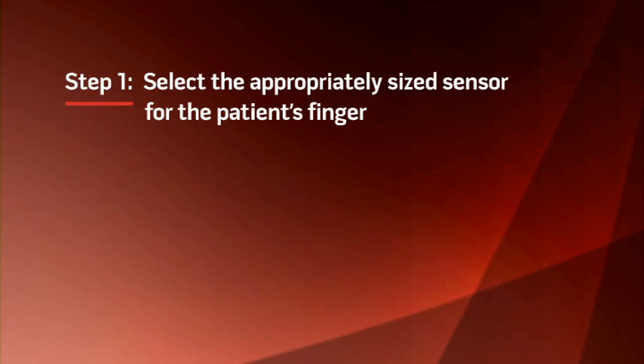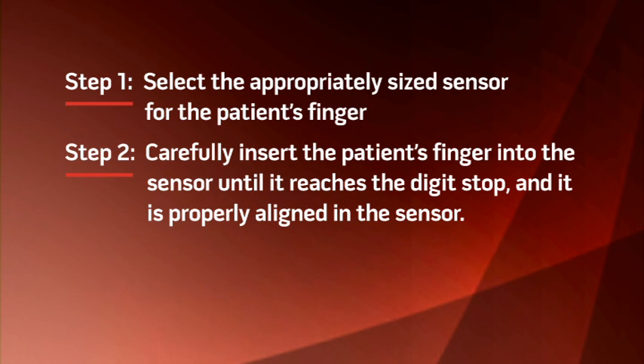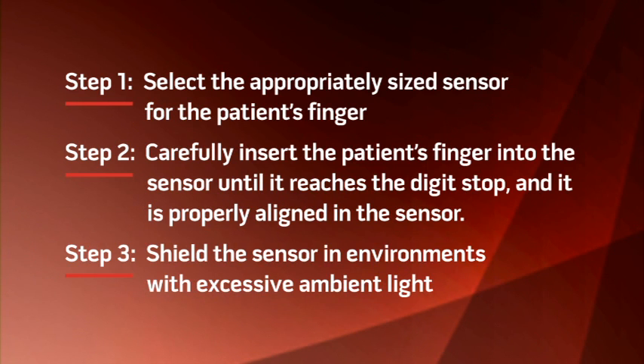So to review, proper rainbow sensor application is achieved by following these simple but extremely important steps. Step 1. Select the appropriately sized sensor for the patient's finger. Step 2. Carefully insert the patient's finger into the sensor until it reaches the digit stop and it is properly aligned in the sensor. Step 3. Shield the sensor in environments with excessive ambient light. For more information about sensor placement and operation, consult the directions for use included with your sensor.